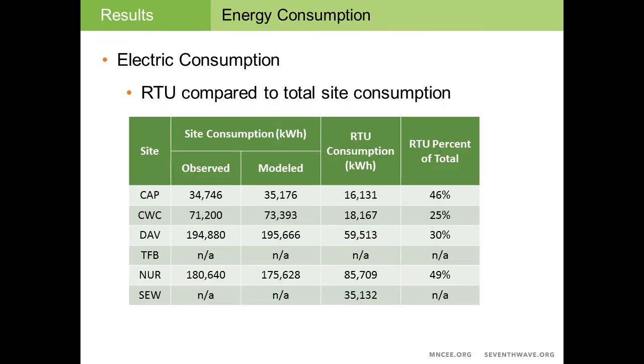So just as with the gas consumption, we compared the electrical consumption of the units with the electrical consumption at the site. And again, we're looking at a variable of what's happening within the site. It varies in range between 25 to 50% rooftop unit to site energy consumption, with no real indicator of whether there is a correlation between a site type and the energy consumption of a rooftop unit.